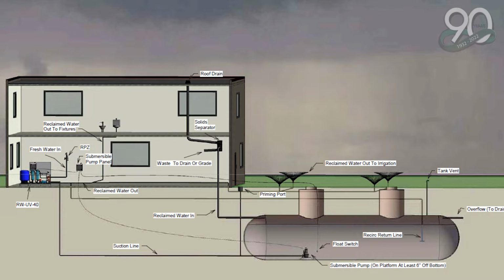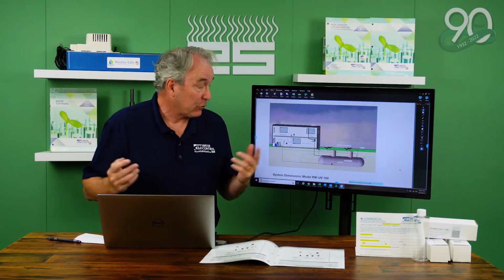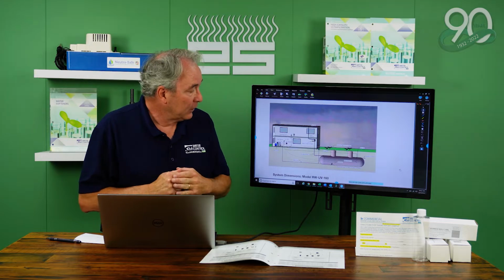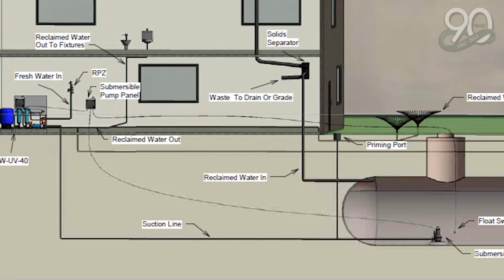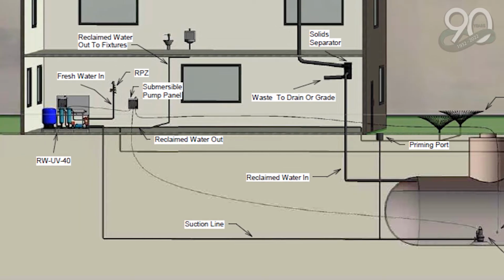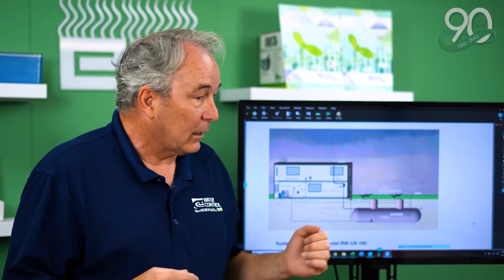When you look at a rainwater harvesting system, you have an infrastructure of roof piping and gutter piping that brings all the water into either a single or, more likely, a series of, in Massachusetts or New England, primarily underground storage tanks. The filtration and delivery side is a skid package with pumps and various sanitation methods to clean the water, keep the water in the tank clean, and then deliver it for its use.